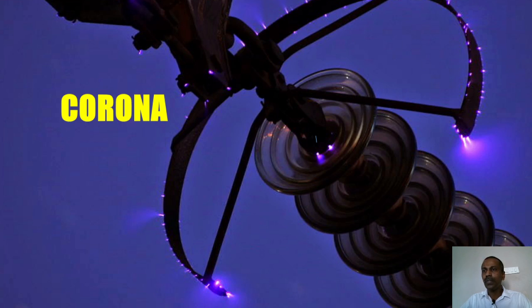ions will be sufficient to collide with the neutral molecules to release electrons from them, and these electrons will collide with another molecule to release more number of electrons. This is a cumulative process. Finally, it leads to the formation of a violet glow along the length of the transmission line. This is called corona.